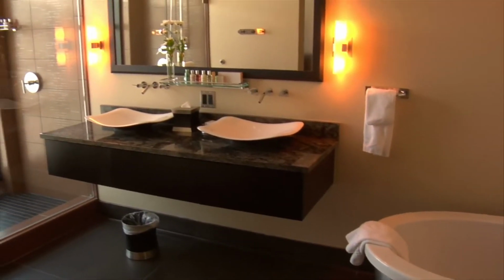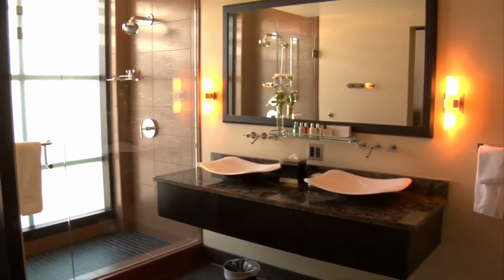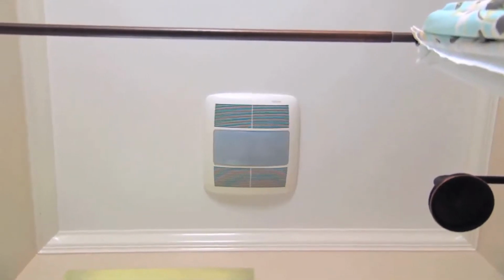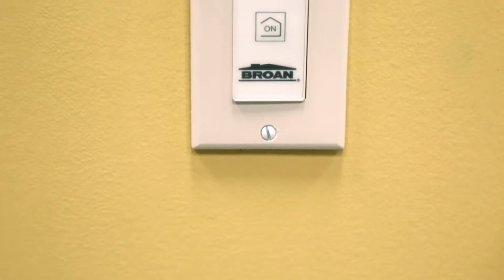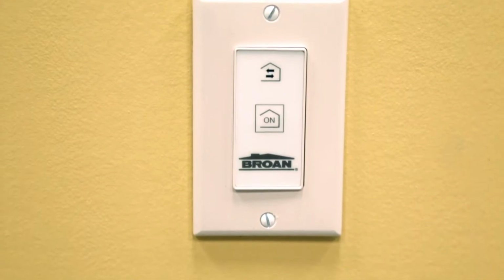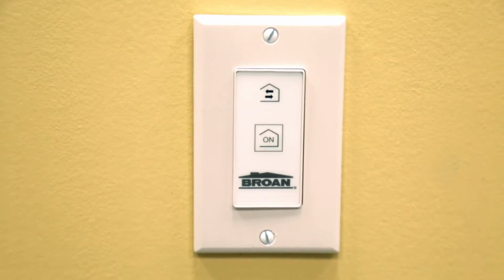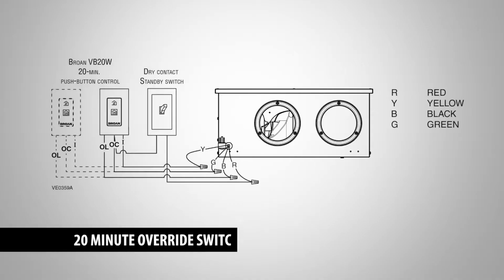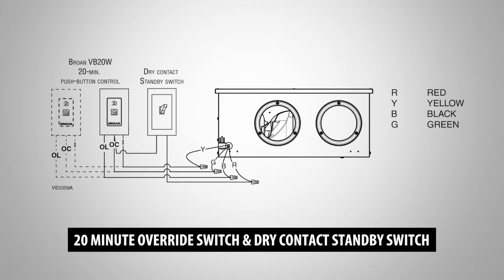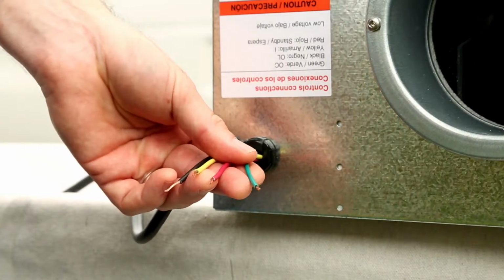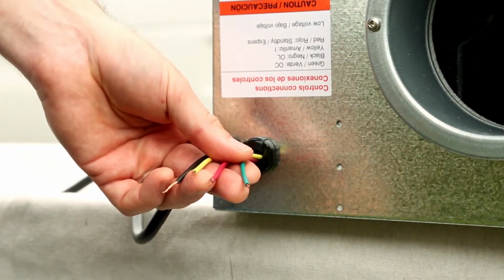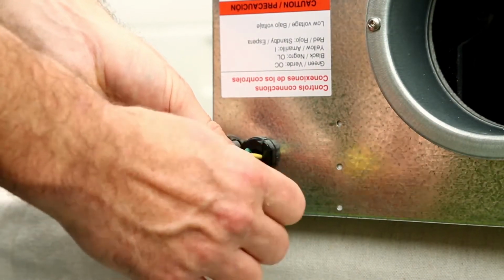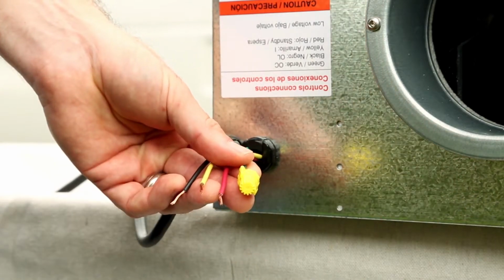When the ERVS100 exhaust register is located in a bathroom, the product can also replace one bath fan. In this configuration, the unit should be connected to a 20-minute override control in the bathroom. Wire the control switch according to the package instructions. Finally, the unit can be connected to a 20-minute override switch and a standby switch. This configuration allows for operation of the override switch even if the standby switch is turned on. The unit comes with red, yellow, black, and green wires. Regardless of the control configuration chosen, be sure to cap all unused wires.